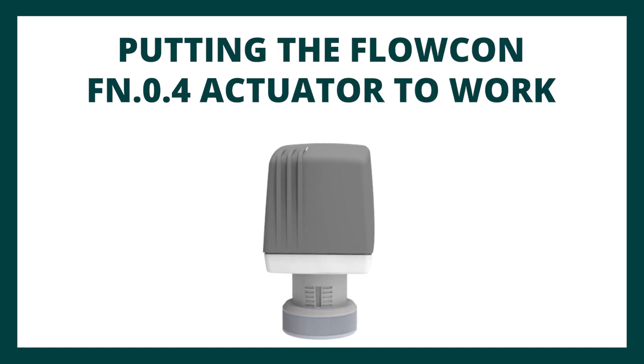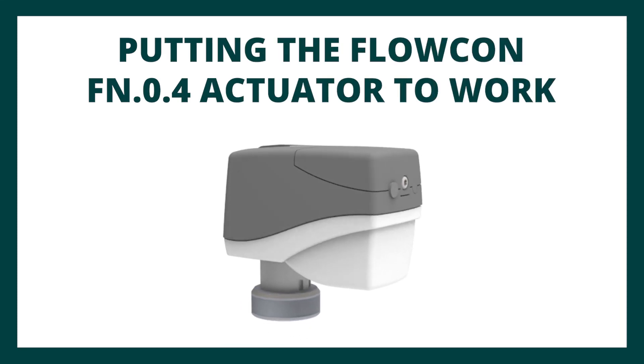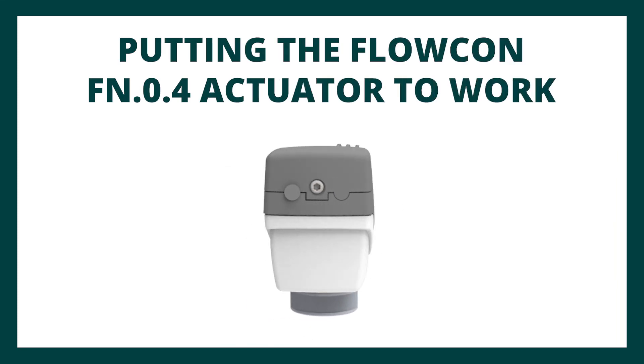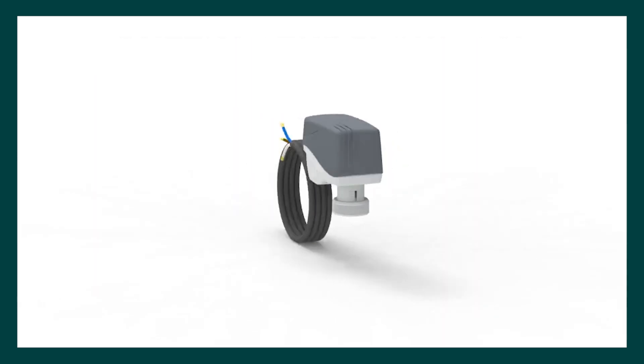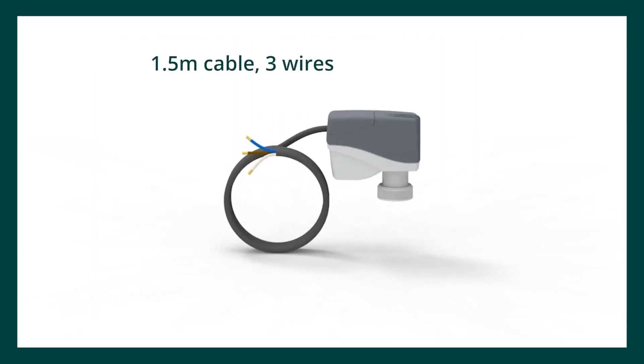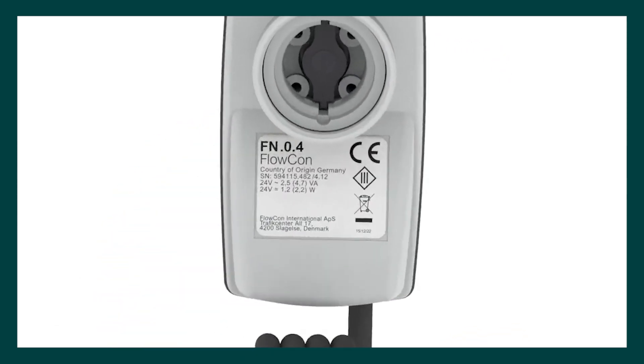The self-calibrating FlowCon FN.0.4 electric actuator is designed for 24-volt AC-DC with 10% tolerance and a 50 or 60 Hz supply with a digital 3-point floating and on-off signal.